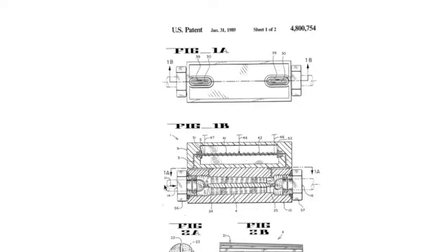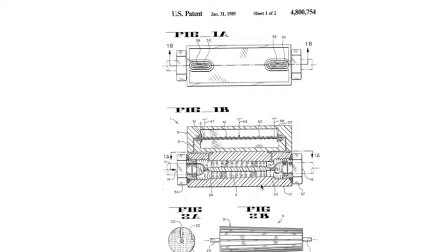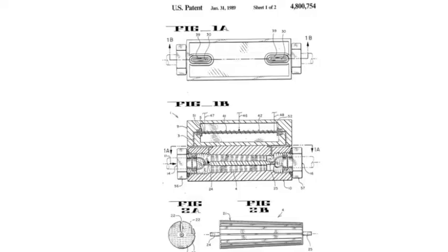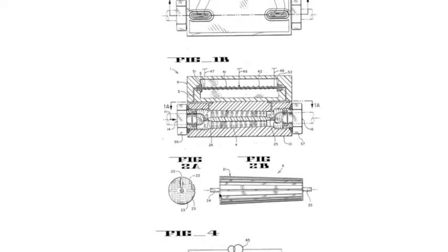Essentially, the flow goes through, some of the flow goes through the sensor, and more of the flow goes through the laminar flow element. The split between the sensor must be a long, thin tube such that the flow within the tube is laminar, and the flow within these elements are laminar.